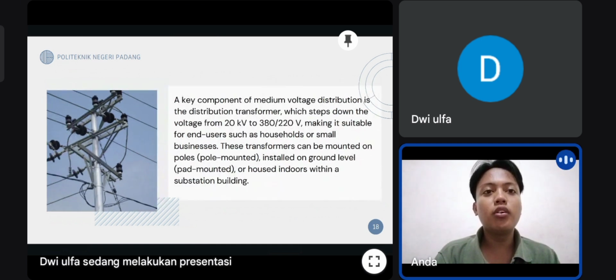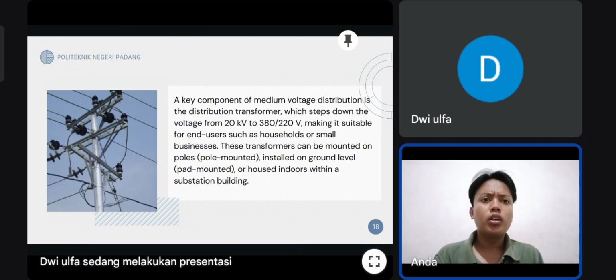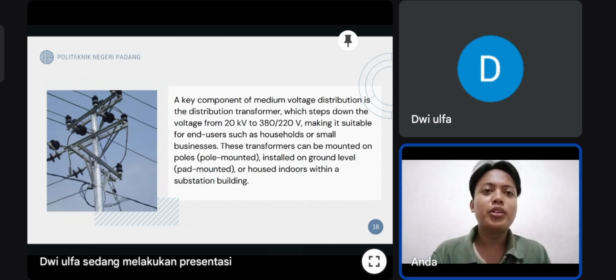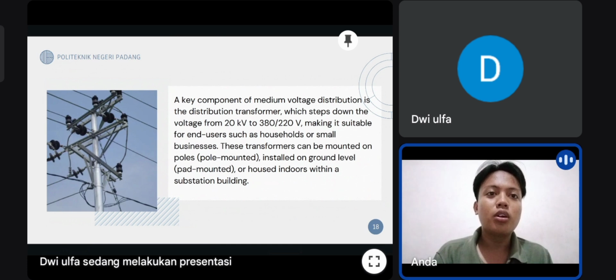A key component of medium voltage distribution is the distribution transformer, which steps down the voltage from 20 kV to 380 or 220 volts, making it suitable for use in households or small businesses. The transformer can be mounted on a pole, installed at ground level, or housed indoors within a substation building.